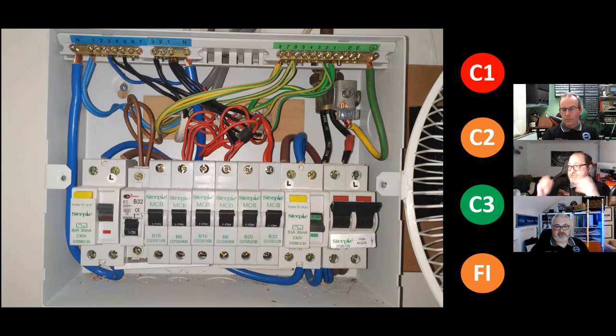But is this just C3 stuff, or is this C2? I'd C2 it. Is the integrity of the earthing affected? Integrity of earthing, so that's a split RCD board, AC type, which you know my views on. I think we'll be coding them C2s and C3s pretty soon. We said that last year, didn't we? We did. Yeah, trust me, everybody, it's coming. You'll be coding AC RCDs whether you want to or not. Yeah.